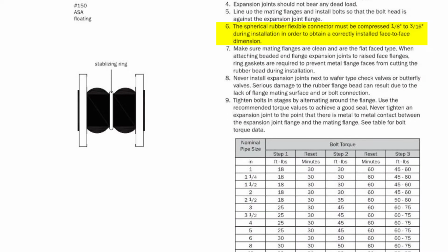The connectors are made slightly longer to help with sealing against the adjacent pipe flanges. It can be a tight fit to get them in place, but once in place, the face-to-face dimension from flange to flange should match the value shown on the datasheet chart. Really important is to make sure the expansion joint is connected directly to ANSI standard bolt flanges immediately adjacent to the joint. There cannot be another component that doesn't have a bolt flange, such as a wafer-type check valve or a butterfly valve, between the expansion joint and the pipe flange to prevent damage to the joint and ensure a proper seal.